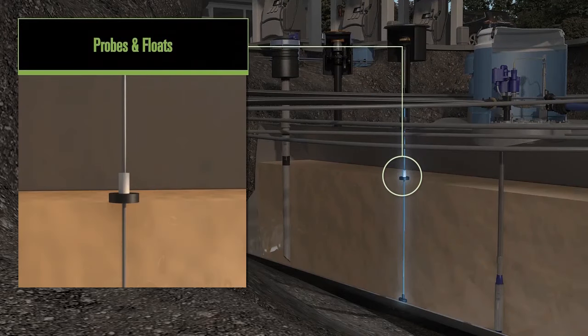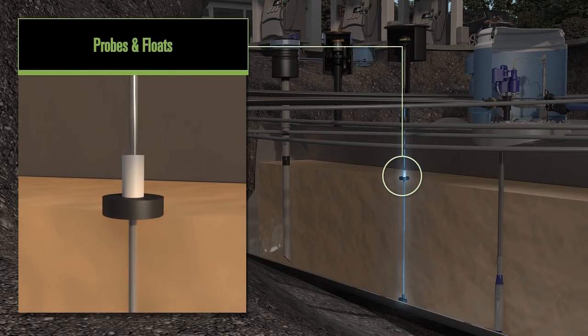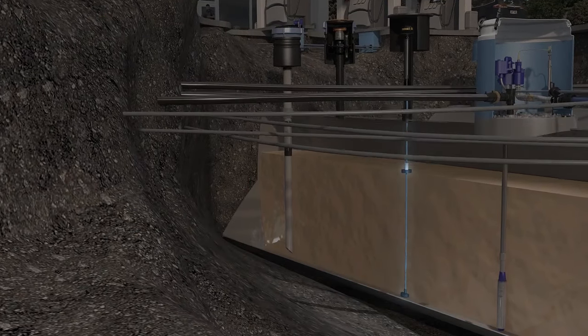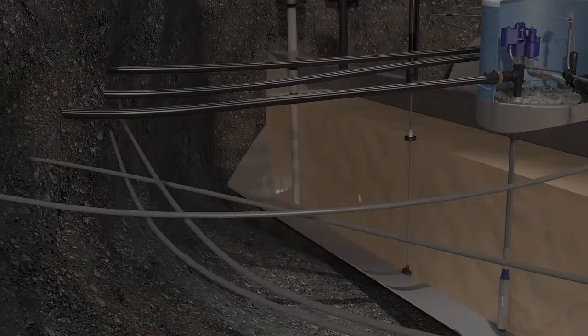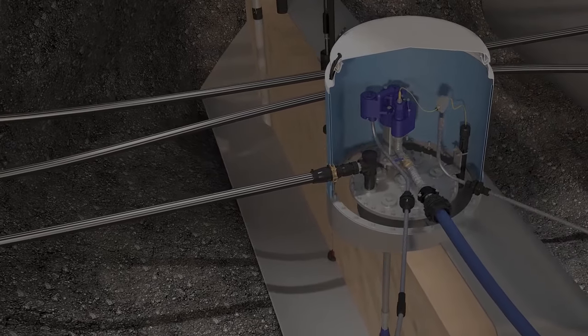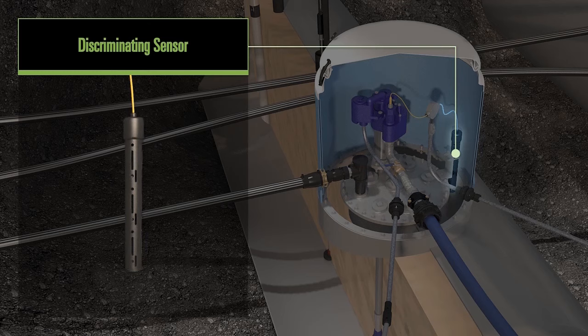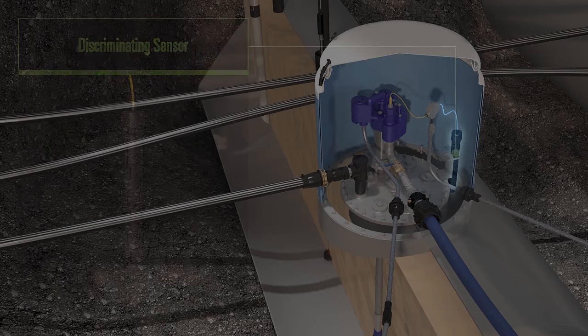Probes work with floats inside the underground storage tank to communicate the level of fuel and presence of water back to the automatic tank gauge. Sensors are placed inside containment areas and the space between the double layer of pipe and containment area called the interstitial space and communicate the presence of liquid where it's not supposed to be.